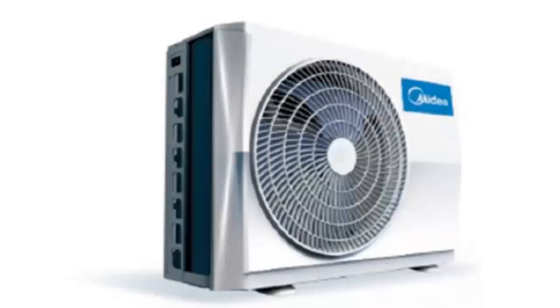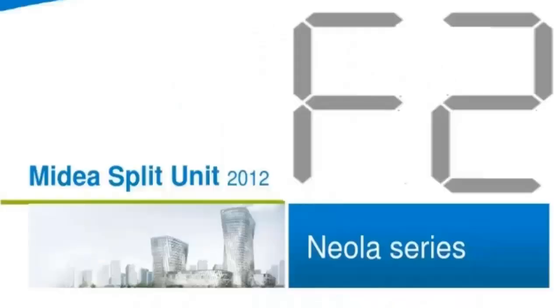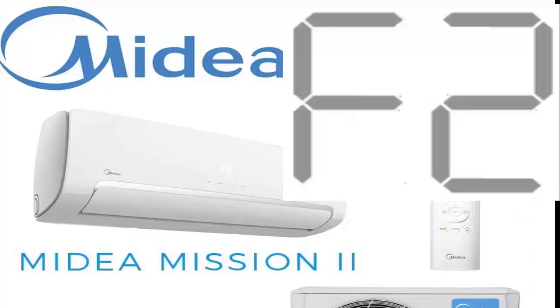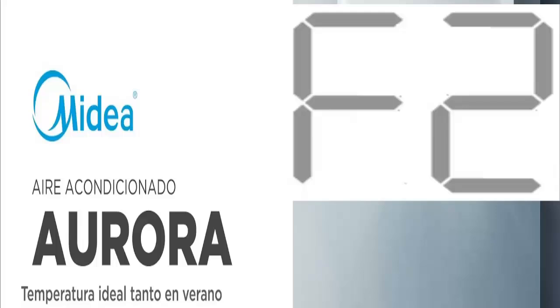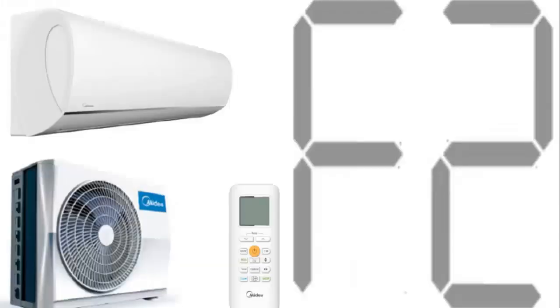4. Condenser temperature sensor. This sensor measures the temperature of the refrigerant inside the condenser. In MIDEA equipment, a fault in this sensor is generally presented when a short circuit or an open circuit is identified. For variable speed inverter MIDEA models from the Neola, Mission, Aurora, and Blanc series, problems with this sensor are identified with the error F2.